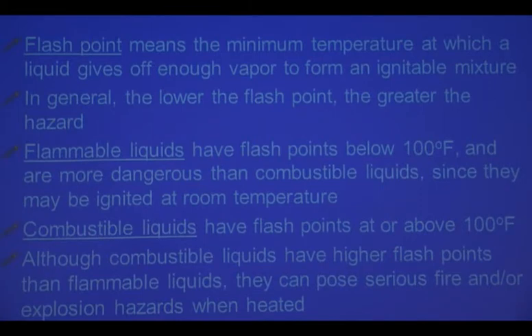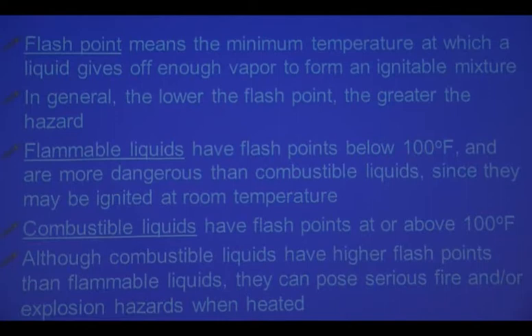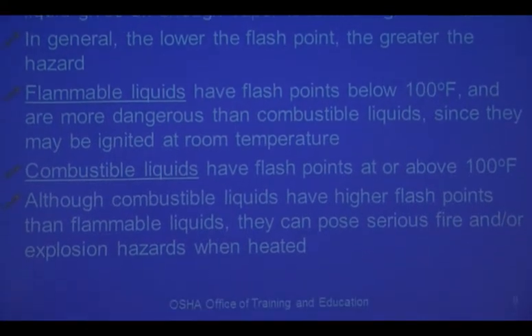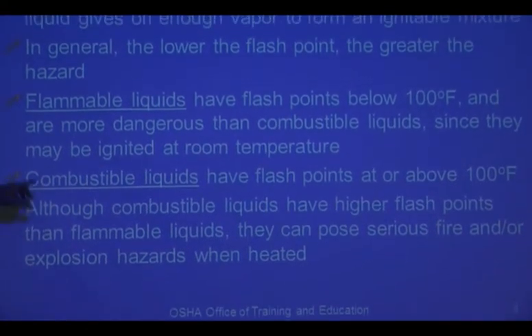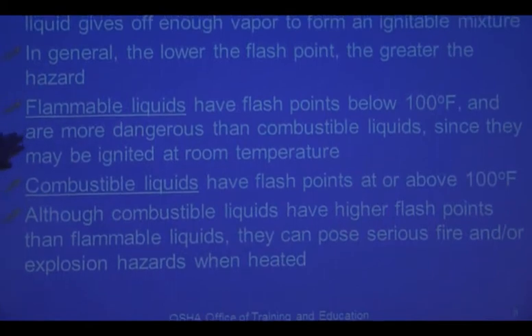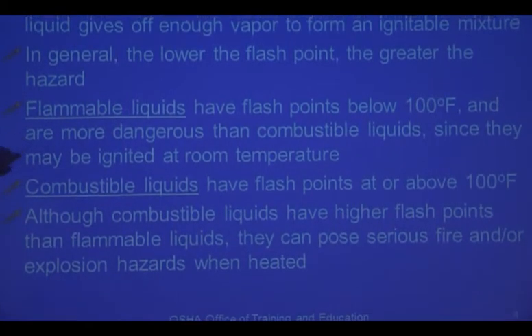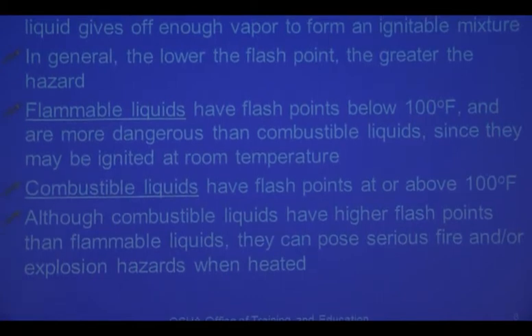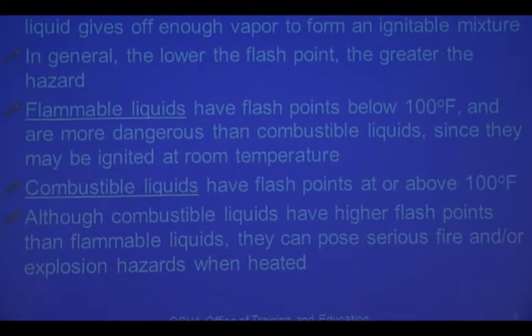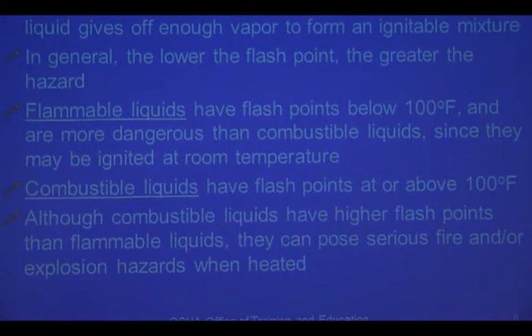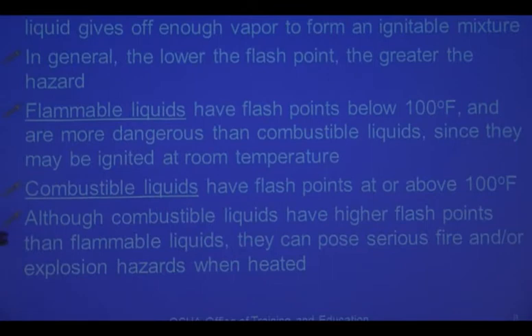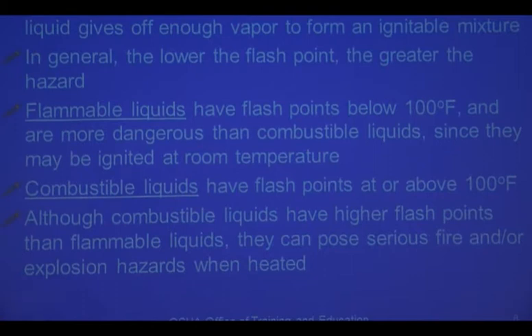A flammable liquid has a flashpoint below 100 degrees Fahrenheit. This is really important — flammable liquids are more dangerous than combustible liquids since they may be ignited at room temperature. Combustible liquids have a flashpoint at or above 100 degrees Fahrenheit. They have higher flashpoints, but still pose serious fire and explosion hazards when heated.